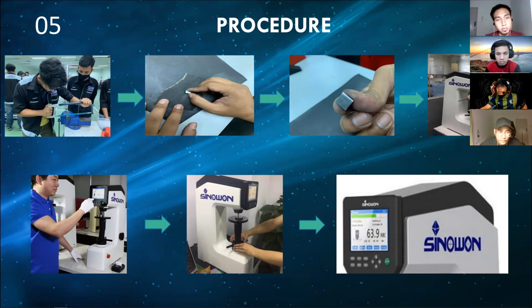Select the ball indenter with a diameter of 1.587 mm and set the preload test force at 10 kgf. Then set the machine parameters by pressing the menu and cancel buttons, and set the parameters of the machine.